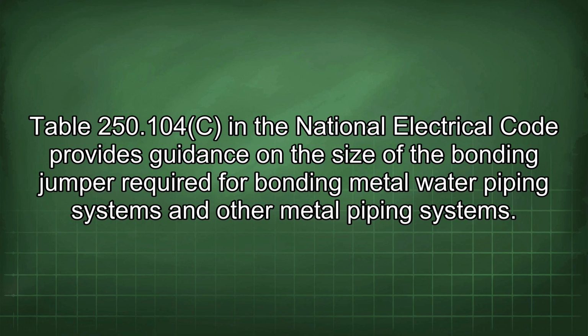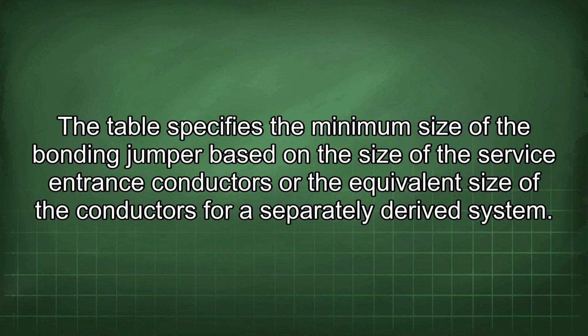Table 250.104C in the National Electrical Code provides guidance on the size of the bonding jumper required for bonding metal water piping systems and other metal piping systems. The table specifies the minimum size of the bonding jumper based on the size of the service entrance conductors or the equivalent size of the conductors for a separately derived system.